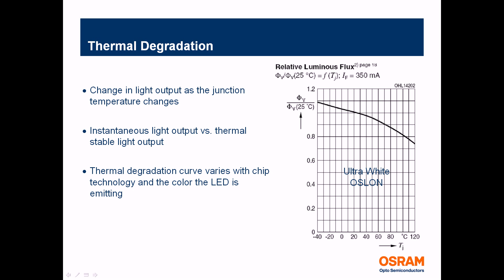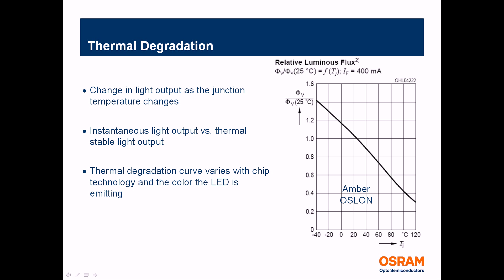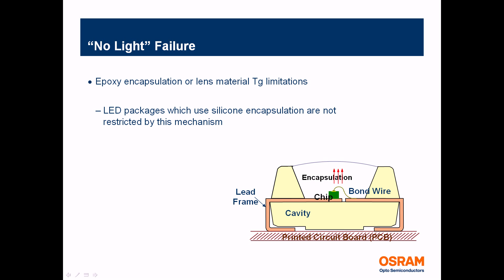Looking at thermal degradation, there's a change in relative light output from the device depending on temperature. LEDs are usually measured at what's called instantaneous light output — a measurement taken at 25 degrees C. However, in actual applications the junction temperature is often much higher than 25 degrees C, so that needs to be compensated for. These curves are found in LED manufacturer data sheets, and they differ for each device and color, so you should look up the specific device and its thermal degradation curve during your design.